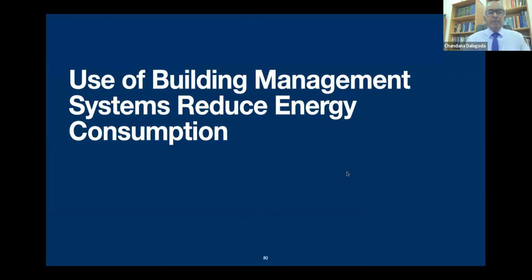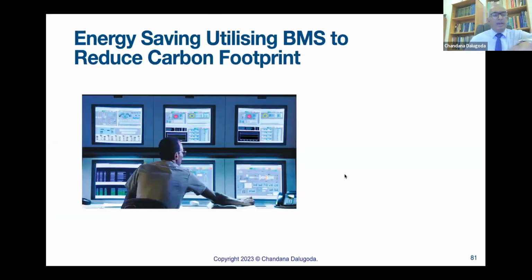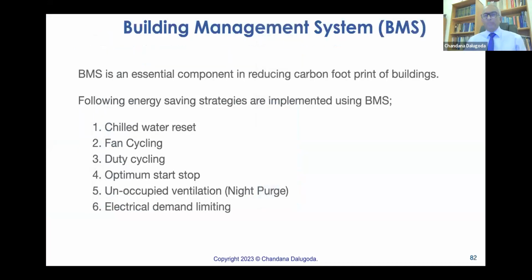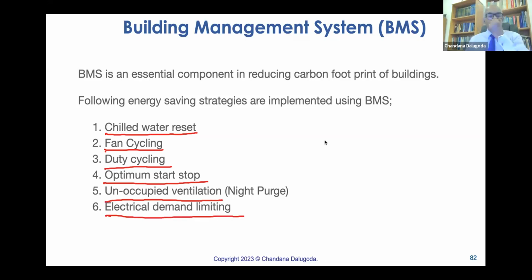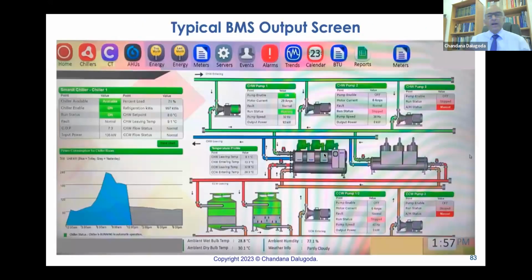So finally, building management systems: how to comply with higher energy efficiency and go to net zero building status. Now, we know we use BMS. Unfortunately, we use it just for monitoring purposes. No, we have certain energy conservation measures through BMS. These are chilled water reset, fan cycling, duty cycling, optimum start-stop, unoccupied mode, that is night purge, and electrical demand limiting. All of these bring about massive savings. We'll take an instant picture.